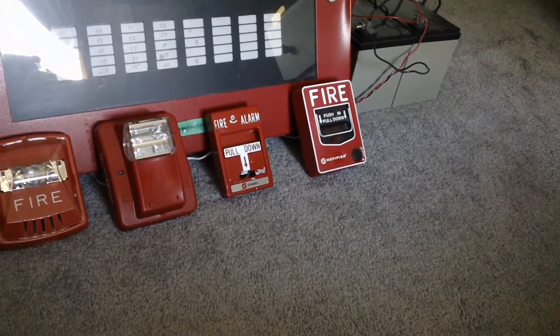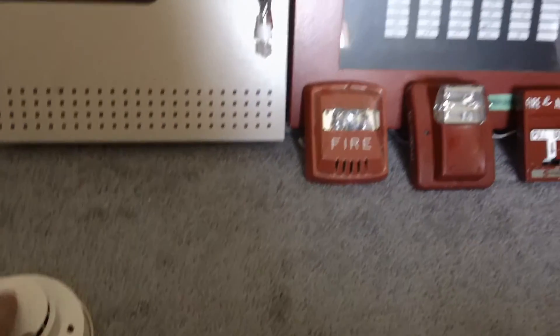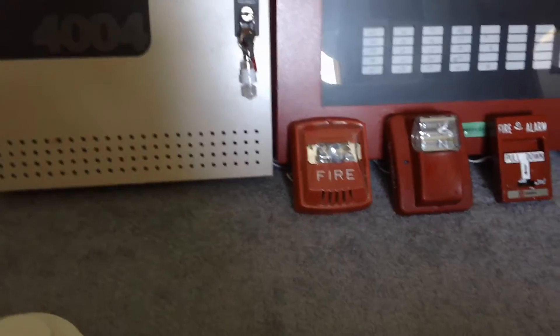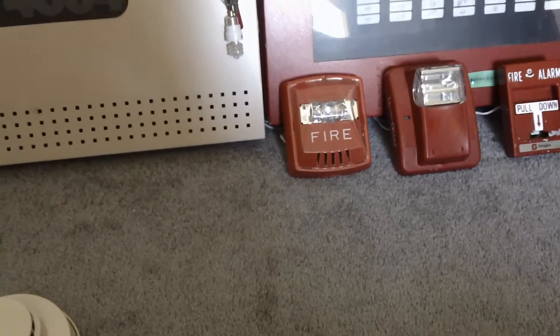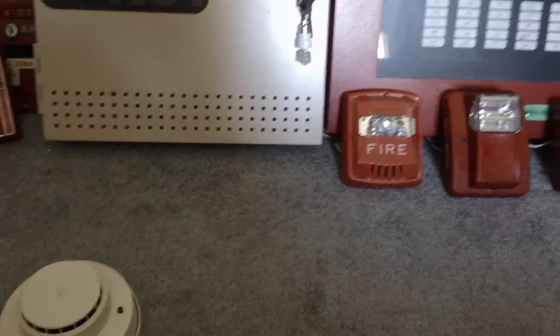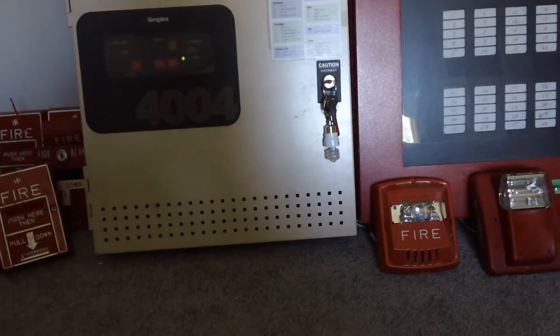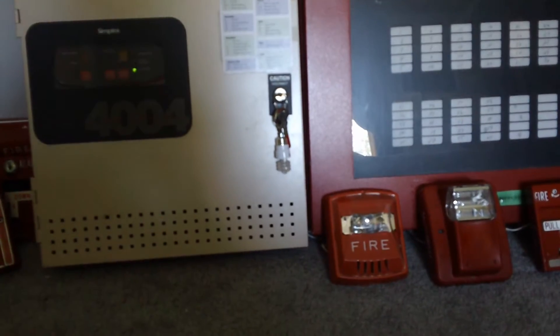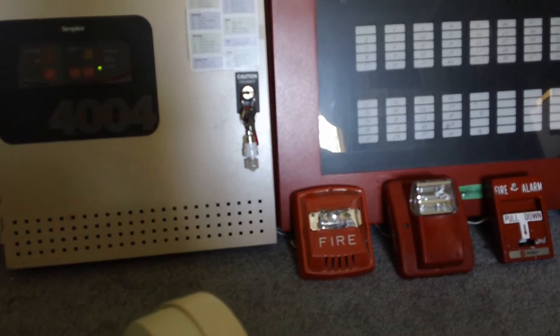I troubleshot a bunch of different things as to why these detectors were not working. So I decided to turn to the fire panel forums, and Andrew — he's the administrator on the forum — told me that I should have checked the compatibility between these two-wire detectors and the 4004. Basically you're not supposed to use two-wire smoke detectors with the 4004 or Simplex panels, and I didn't know that.